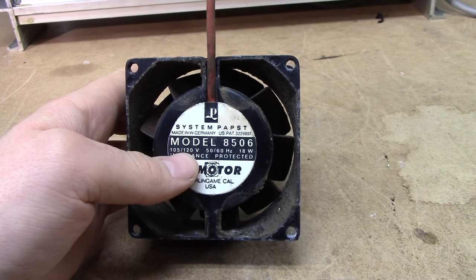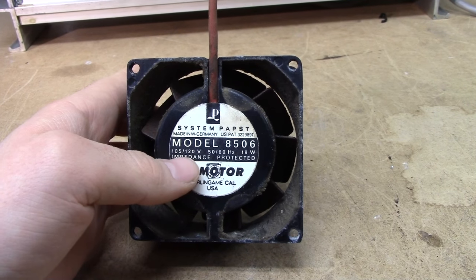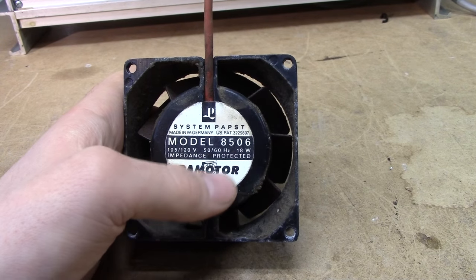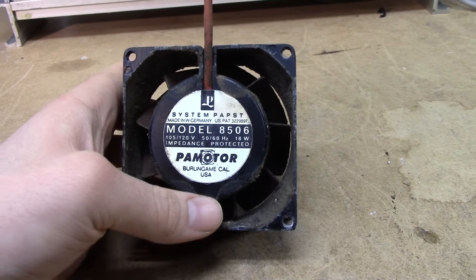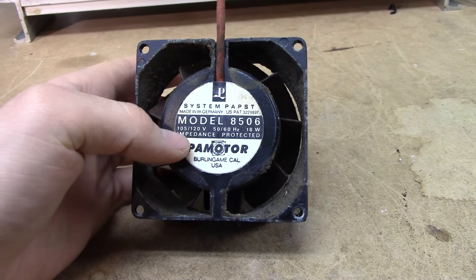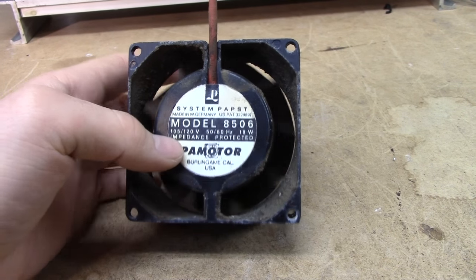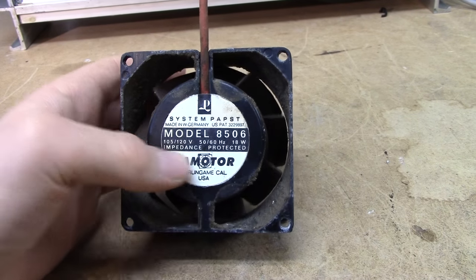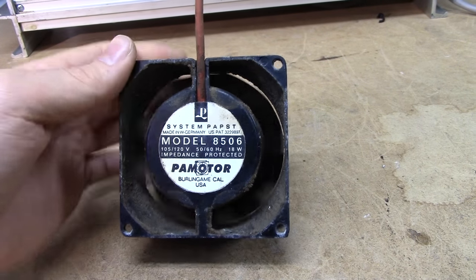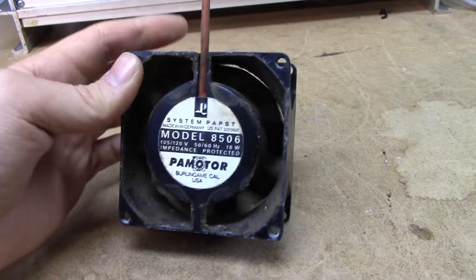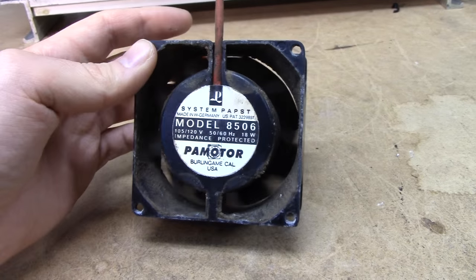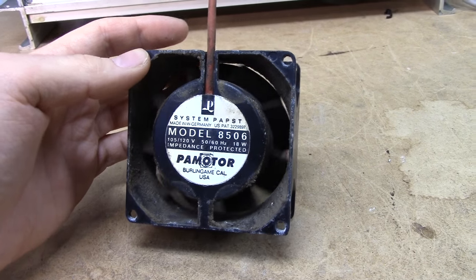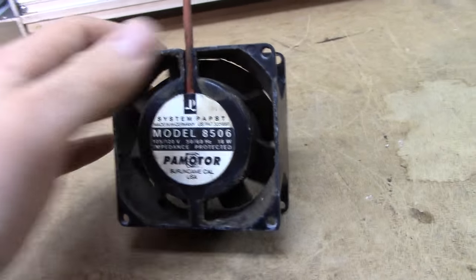But it's a 120V model rated at 18W, so this thing's been running at 50Hz, which has been specified for it, but it's probably not really its best efficiency point.